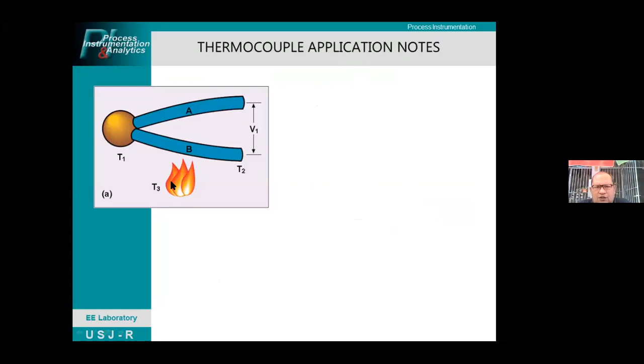Thermocouple application notes: considering when the metal at point B is heated, where the temperature is inserted here, the voltage is not affected in the wiring between the input and output ends. But if the temperature T3 is high enough to melt the insulation of the conductor, it matters, because it becomes a bare wire. But a certain temperature that cannot melt the insulation of the conductor does not affect the terminals here, unless you increase the temperature of the joint between the two different metals, which changes the voltage across here.